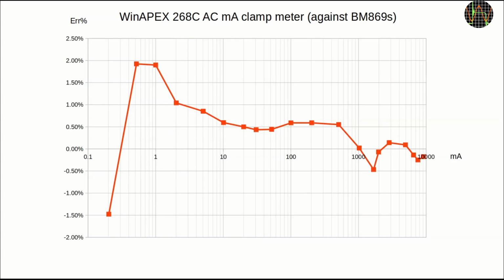The extremes at the low current end are caused by the limiting resolution of the 268C, where a single digit difference is having a huge effect on the error percentage. Overall, this looks pretty good, especially considering that this is a true RMS measurement and a bandwidth of 2 kHz.